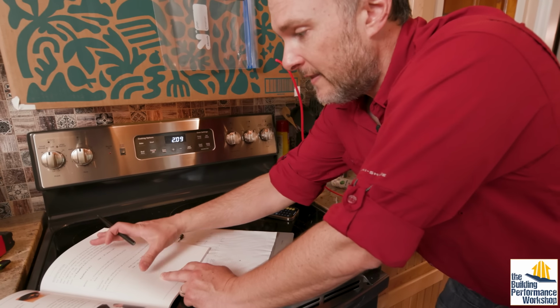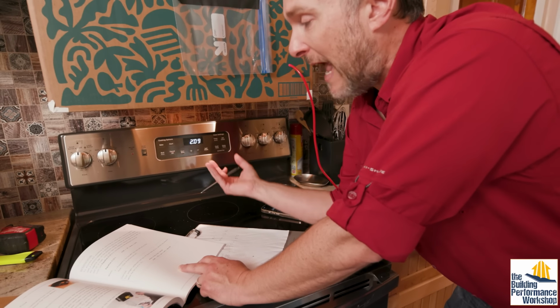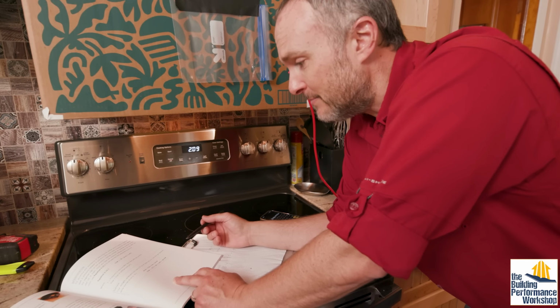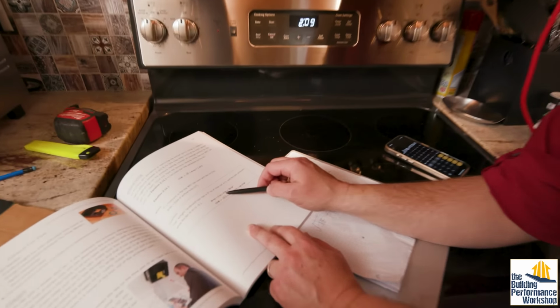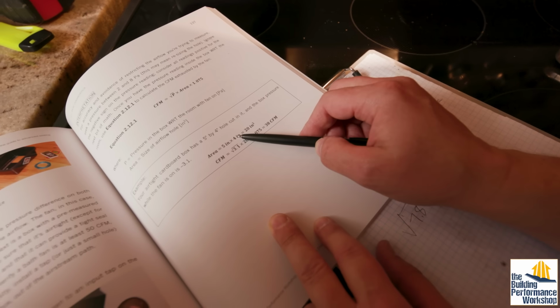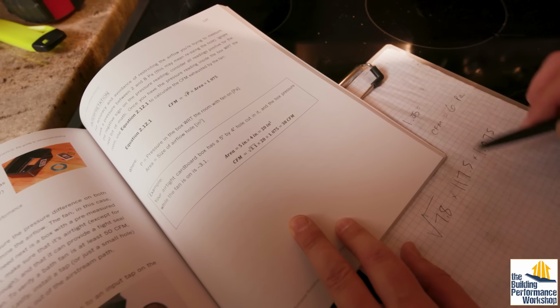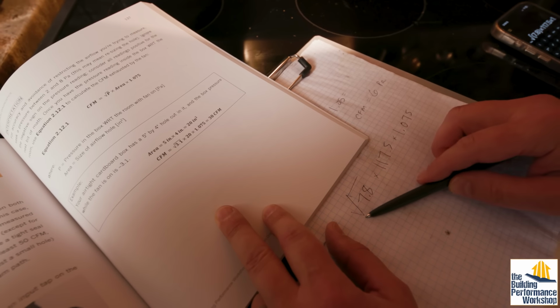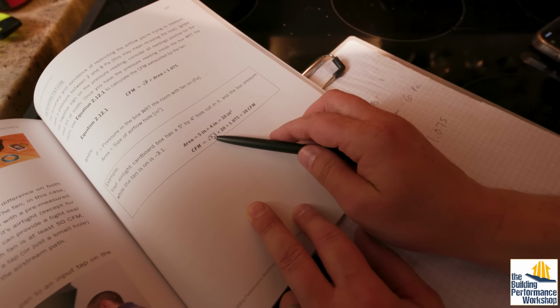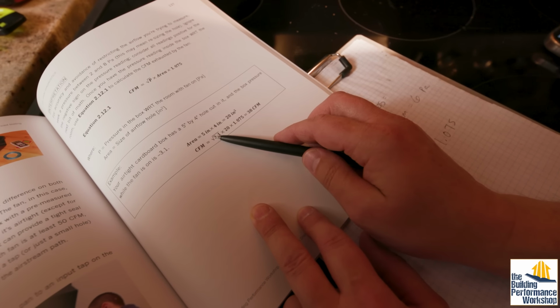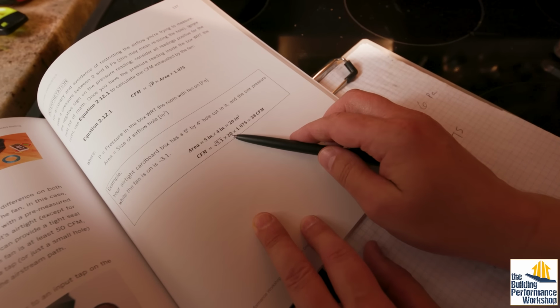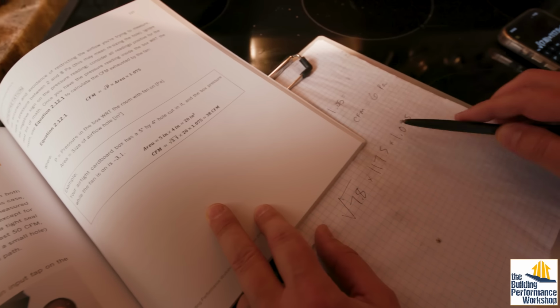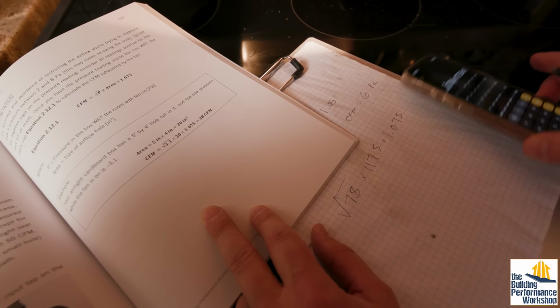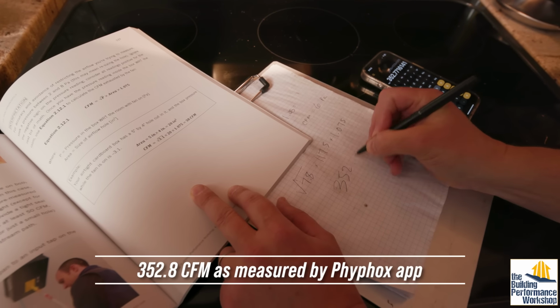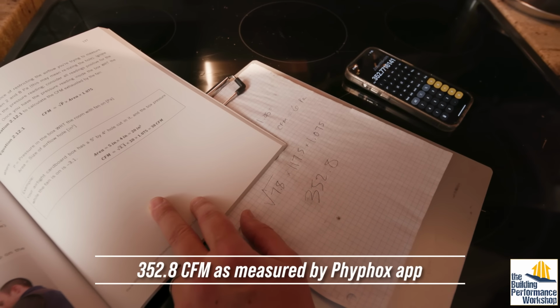So now we have to do math. So the calculation for finding out how much airflow in CFM is going through this box is you need to take the area of the box first, which we know is 10 inches by 11 3/4 inches, which is 117.5 square inches. And then to get the CFM, we do the square root of the pressure inside the box while the fan was on, times our area, which again is 117.5, times our coefficient, which is 1.075, and we get 352.8 is the CFM that we have then calculated for this.